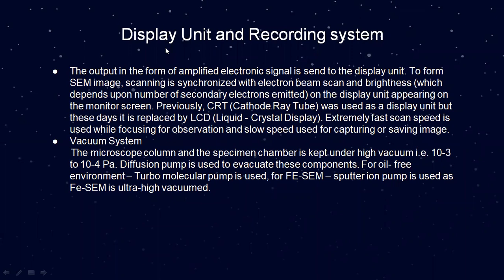The last point: display unit and recording system. The output in the form of an amplified electronic signal is sent to the display unit to form the scanning electron microscope image. Scanning is synchronized with the electron beam scan, and brightness depends upon the number of secondary electrons emitted, appearing on the monitor screen. Previously, a CRT (cathode ray tube) was used as a display unit, but these days it is replaced by an LCD (liquid crystal display). Extremely fast scan speed is used while focusing, and slow speed is used for capturing or saving images. The microscope column and specimen chamber are kept under high vacuum of 10⁻³ to 10⁻⁴ Pascal. A diffusion pump is used to evacuate these components for an oil-free environment.